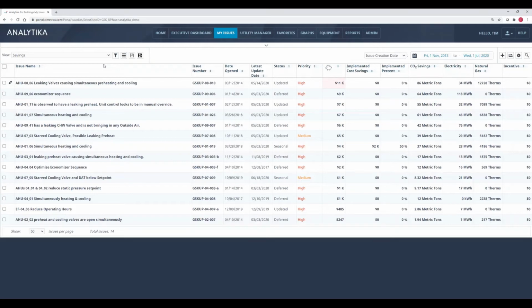So we can. I'll take that in reverse order. Yes, we're very careful not to double dip. If there's a coil problem and a damper problem on the same air handler, we're very careful to tease those apart and make sure that we're not double dipping on savings, because if you fix one, you're still going to have the other issue, and you don't want to consider the savings to come from both. So our energy engineers are very careful about not double dipping on savings when there's multiple issues on the same piece of equipment. And I'm sorry, what was the first part of the question again, Lexi?